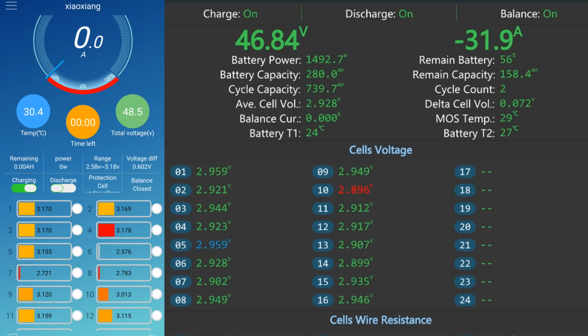We are under 47 volts now with the new battery. And the QUCC battery is at 48.5 volts. That's interesting, right? It has a higher voltage, but there's no juice in the cells anymore, so it stays disconnected. And this is why the relay doesn't turn on anymore, because the outside voltage is at 47 volts now, and the battery itself has 48.5, so it doesn't recognize this as a charging current or charging voltage at all.